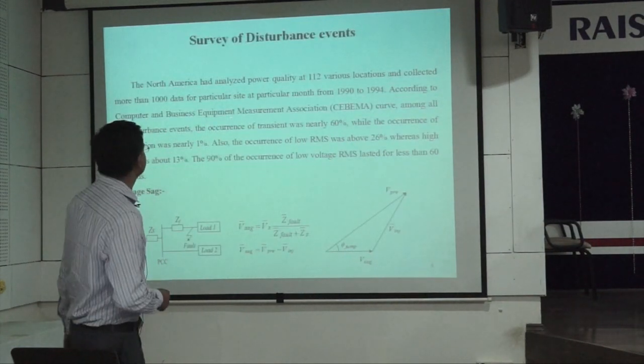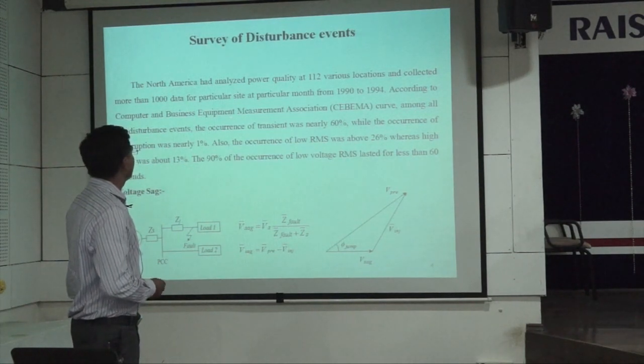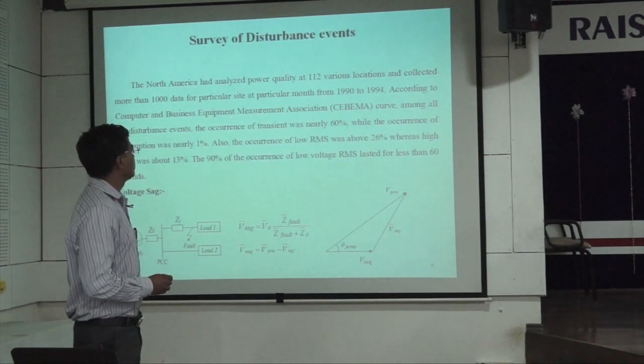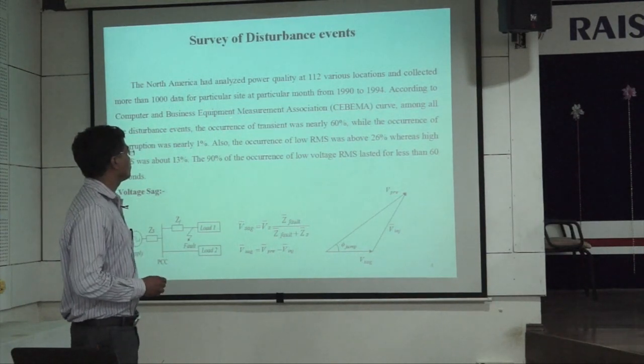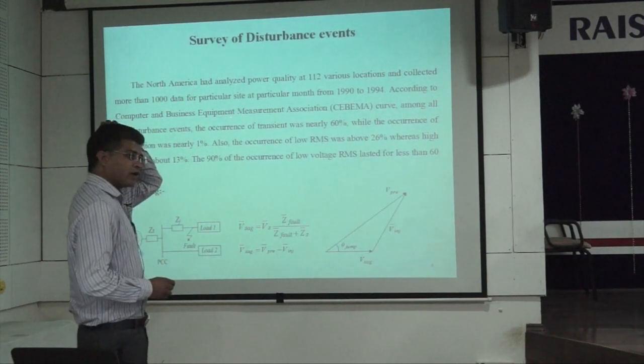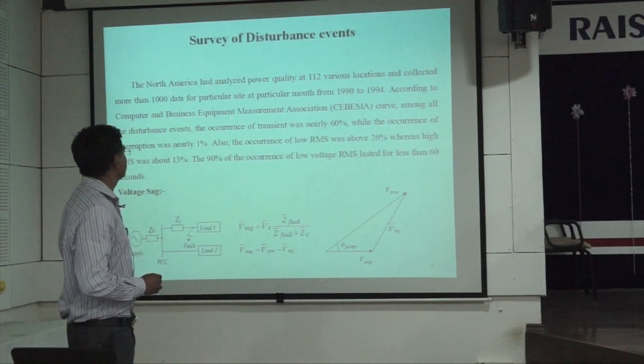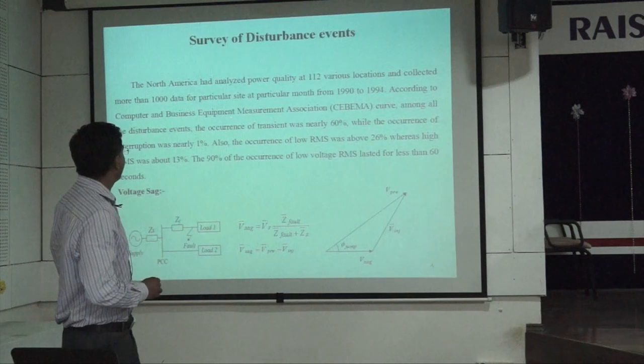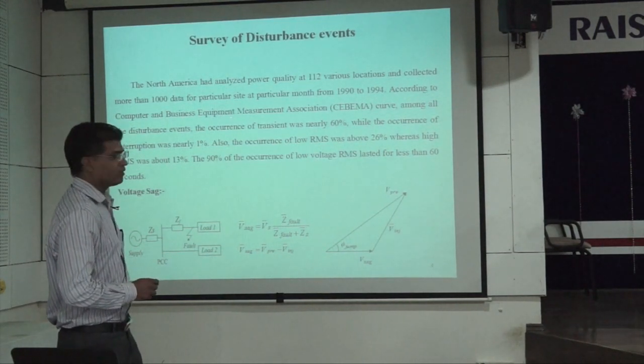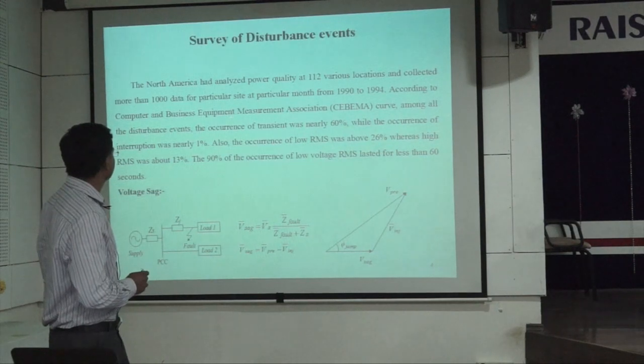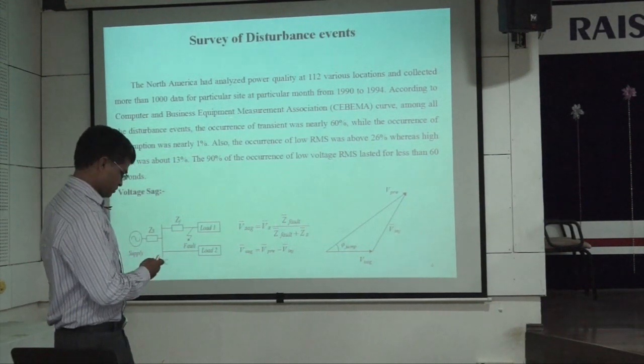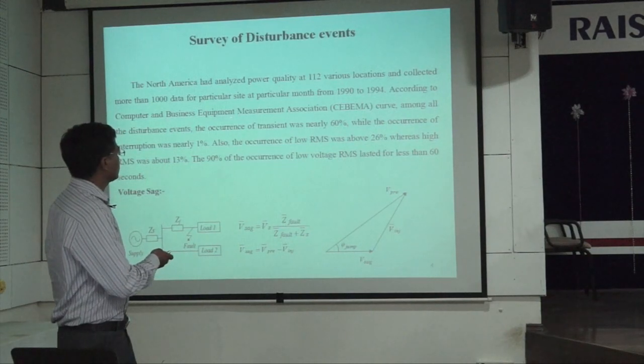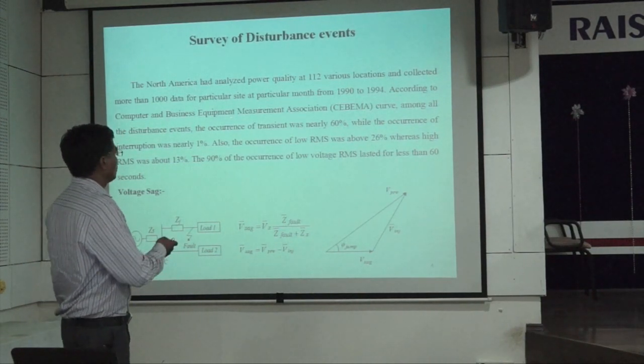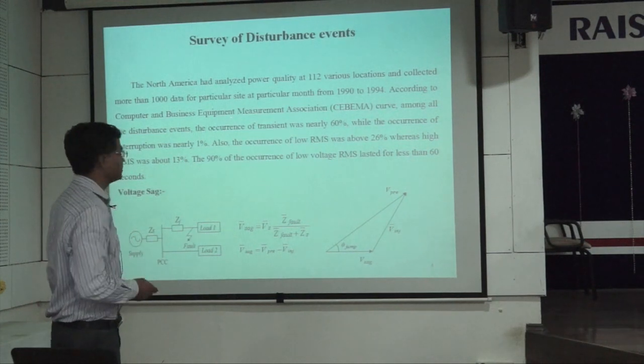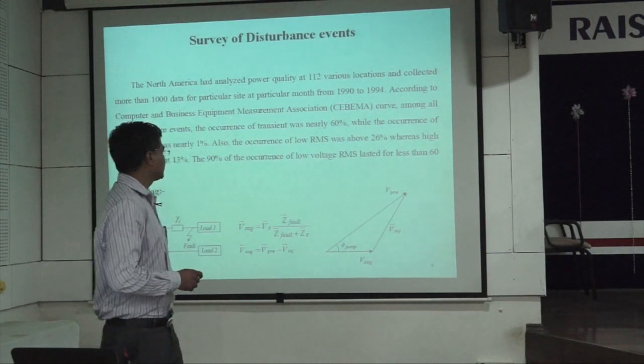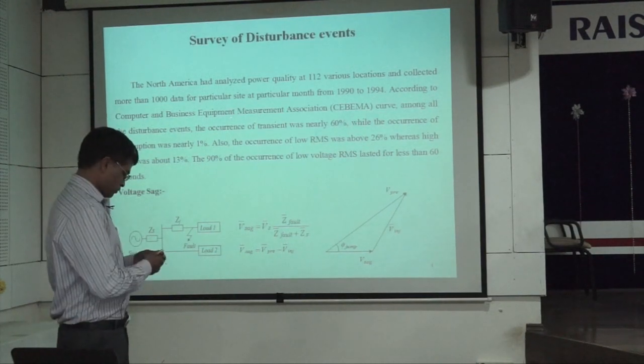The survey of disturbance events has been done in North America, for around 1000 data from about 112 various locations, in the years 1990 to 94. According to the CBEMA curve, Computer Business Equipment Manufacturers Association curve, among all the disturbances, the occurrence of transients was around 60%, while the occurrence of interruption was 1%, and the occurrence of low voltage is about 26%, whereas high RMS is about 13%. 90% of the occurrences of voltage RMS variations lasted for less than 60 seconds.